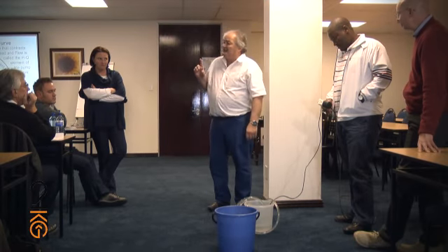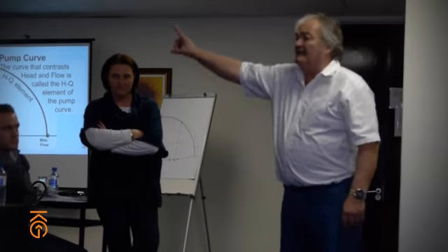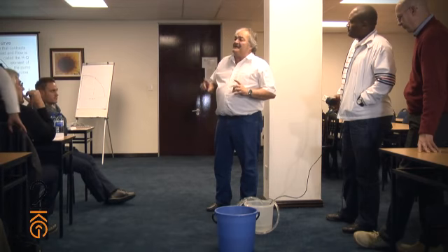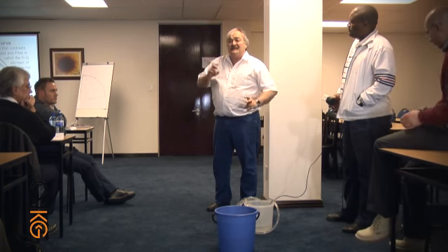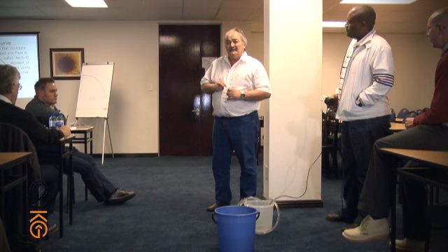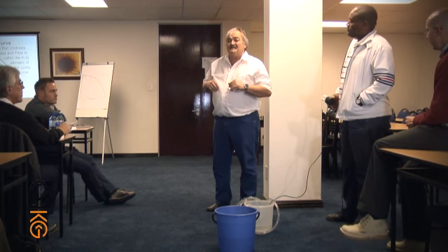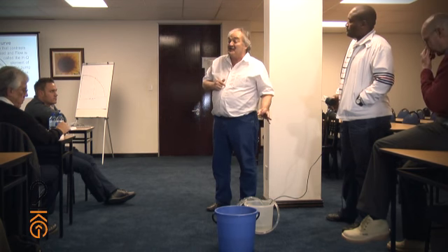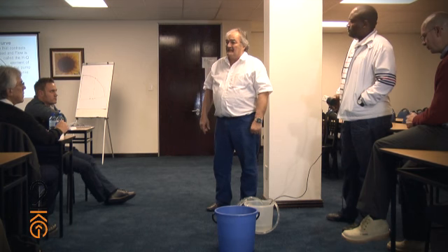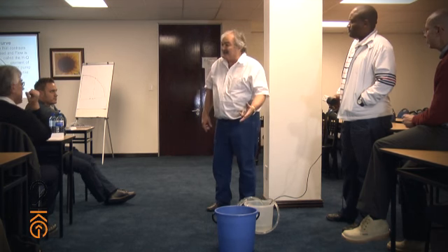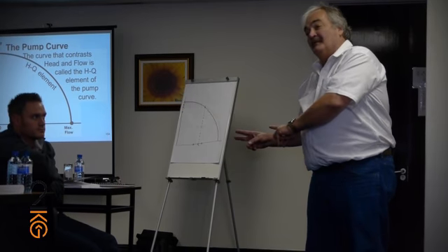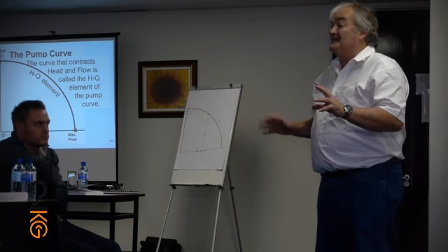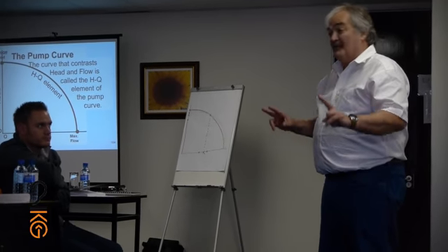Now, I've shown you that pumps move all over their curves, just as the system changes. We see that the discharge head is a function of the suction head. As the suction head rises, the discharge head rises. As the suction head drops, the discharge head drops. If the suction head drops too much, the pump goes into cavitation. Then I have the option of either bumping up the energy coming into the suction or restricting the flow. Your operators govern whether your pumps are problematic or whether your pumps behave.